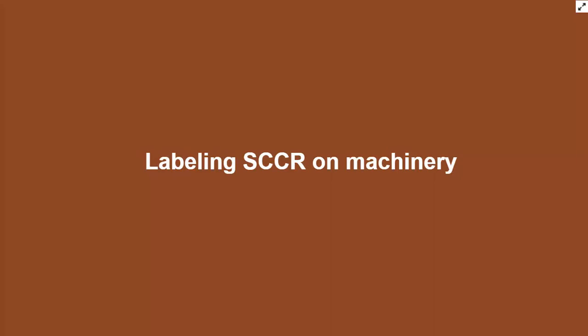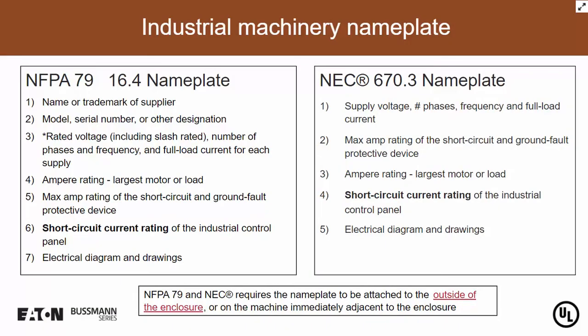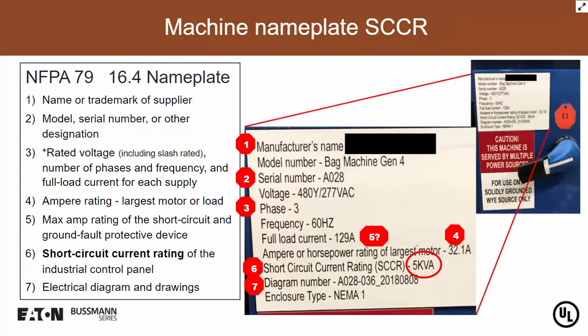Well, now that you've determined the short circuit current for a piece of machinery, how do you comply with the requirements for labeling? Well, I had previously identified the paragraphs and sections in NFPA 79 and the NEC that cover the requirements for the labeling. So we've covered this already. I think it's pretty clear what kind of information needs to be provided on that nameplate. So let's take a look at a typical nameplate.